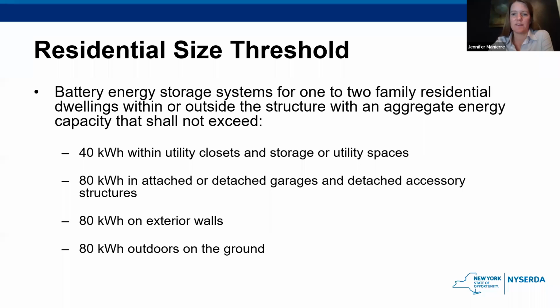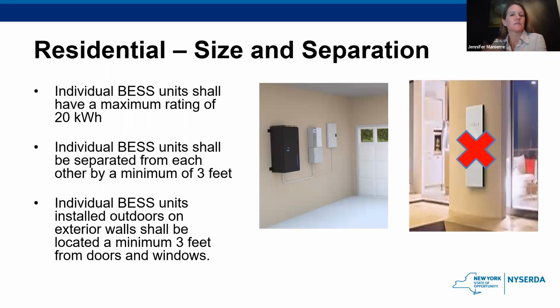Anything above that, you're going to be triggering the commercial code, essentially. Size and separation for residential systems: each individual unit has to have a maximum rating of 20 kilowatt hours. They need to be separated from each other by a minimum of 3 feet. Many of these things are probably sounding familiar to you by now. And units that are installed outdoors on exterior walls need to be at least 3 feet from doors and windows.